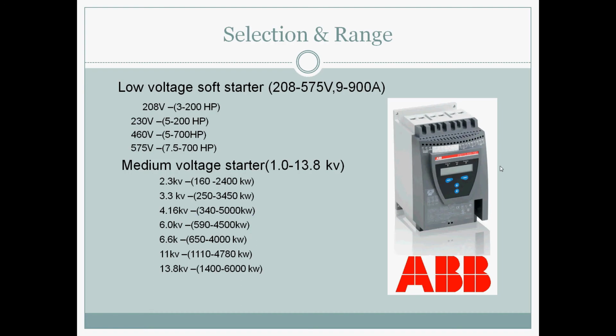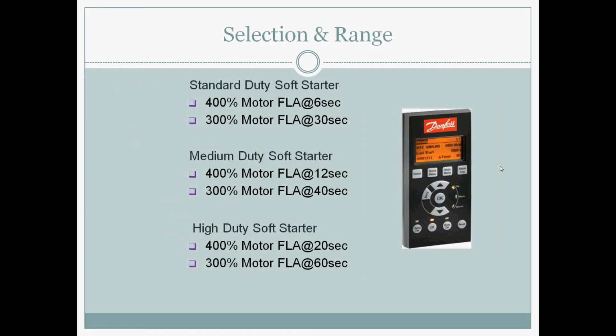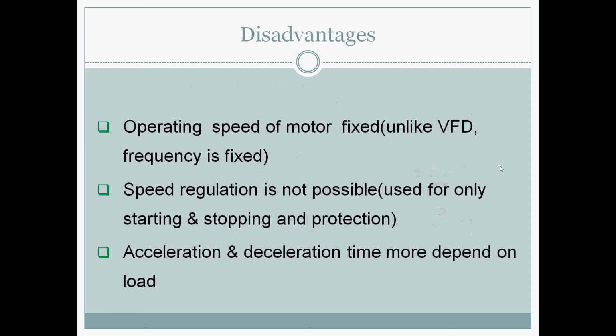Selection and range. Low voltage soft starter from 200 volts to 575 or 600 volts. Medium voltage 1 kV to 13 kV. Rating is given. I preferably use ABB. Selection and range for a standard duty soft starter is 400% motor FLA, 300% of motor FLA for 30 seconds. Medium duty soft starter, similar thing, and for high duty. So you can use it for three different ranges: standard duty, medium duty, and high duty.